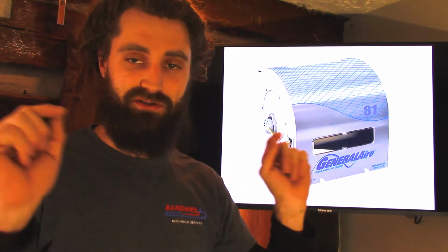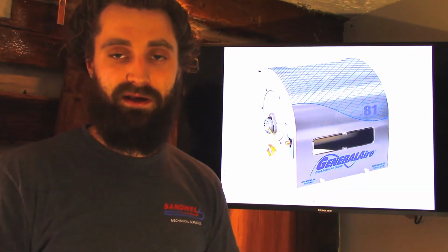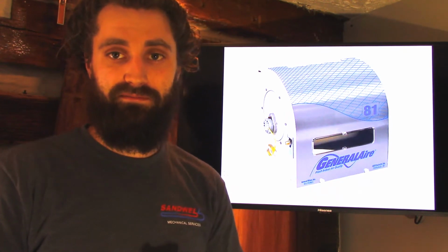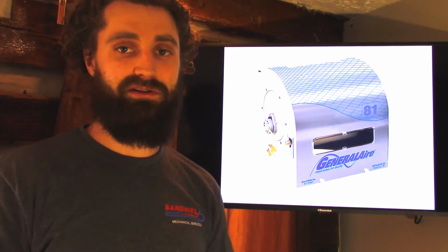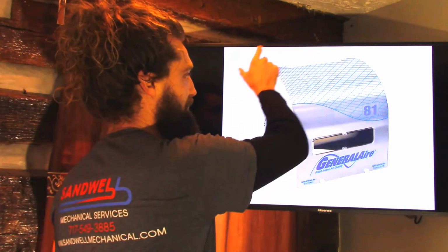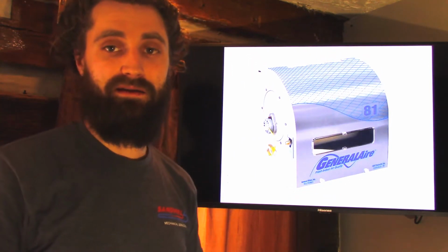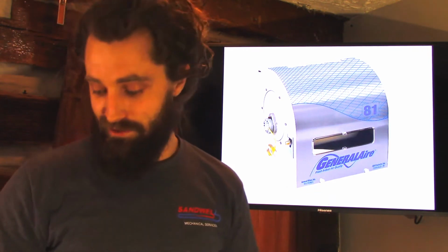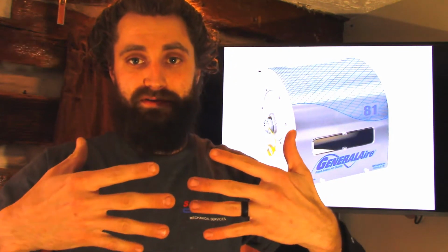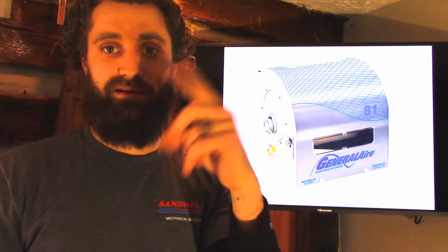Whenever this thing is installed, if you have sheet metal ductwork, great, you can put it on the ductwork, screw it in, seal it up, you're good to go. If you've got fiberglass duct board on your supply or return plenum, make sure the technician has put in a sheet metal backing plate, because I've seen where the weight of these units, when they get full of water over time, will start to fall off the fiberglass, and now you've got your humidifier on the floor with a little quarter-inch hose squirting water everywhere, and that's a call to the insurance company.